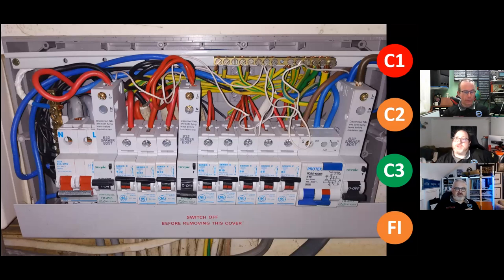Okay, so we've got lots of it could be improved, but is anything in here the smoking gun for potentially dangerous? C2. I'm going to go with... I would work it to a C2 with the strain on the conductors. Those tails, they look like there's a lot of strain in there. I'm not comfortable with those. No, I'm not at all.